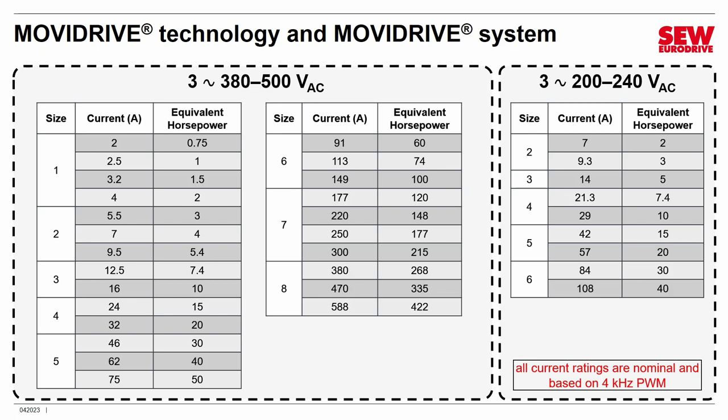These ratings are nominal and are based on pulse width modulation at 4 kilohertz, which is the lowest frequency. At 4 kilohertz, PWM is audible to some people, so in some settings — like a quiet environment such as a theater — you have to switch the VFD to a higher frequency so it can't be heard. When you do that, the drive runs a little hotter and you have to derate these numbers. But at 4 kilohertz in a factory environment where it's already noisy, these numbers apply.